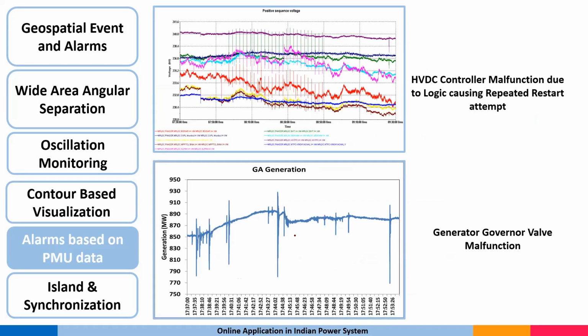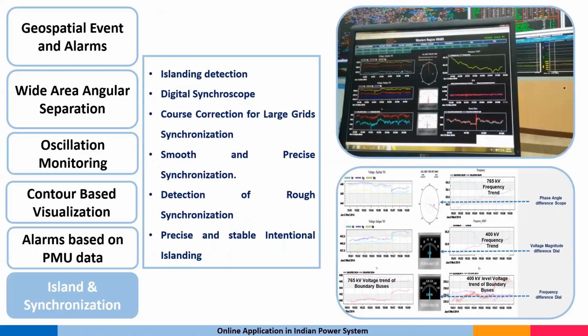Any specific phenomena can also be seen, like any problem with the valve, generator problems, or any HVDC controller malfunction. And we can have the digital synchroscope also. We can utilize this because we have the voltage and current phasors, so phasor information is available in real time, right? If you have the phasor information from the different nodes, the line voltage or the bus voltage, you can utilize it like the substation does, using the voltage across the breaker to synchronize it. You have one voltage from the bus side and one voltage from the live line side, and if you want to close the breaker, you can utilize those voltages to know whether you can close the breaker or not. Earlier, this was possible only from the field. Now you can easily do it at the control center level also.